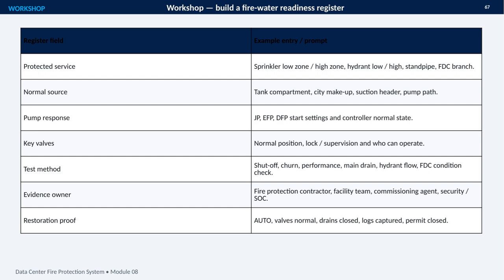Then document its normal water source and the expected response of the jockey, electric, and diesel fire pumps, including their start settings and controller status. The register should also make valve control unambiguous. Record each key valve's normal position, how it is supervised or locked, and who is authorized to operate it. For testing, specify the method, whether that is a shutoff, churn, performance, main drain, hydrant flow, or FDC condition check.